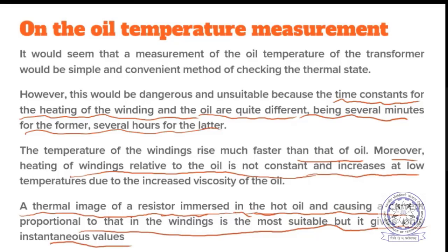People are trying several methods for monitoring the condition of the transformer. No, sir, what I'm trying to ask is, if you are supposed to measure the temperature of the winding, then why are we using a thermal image of a resistor in oil? Directly measure the temperature of the winding, and for oil directly measure it through some instrument. Why are we transferring it to oil for measuring the temperature of the winding, sir? That's what I'm not getting, sir.